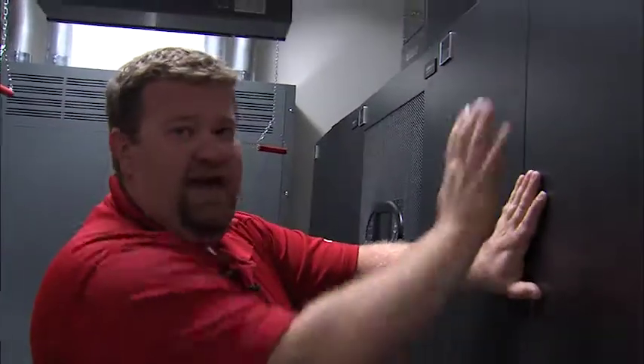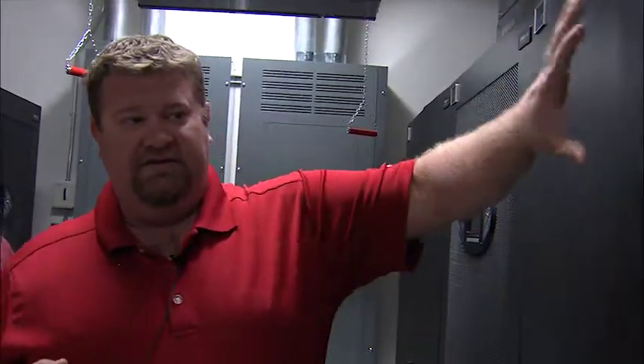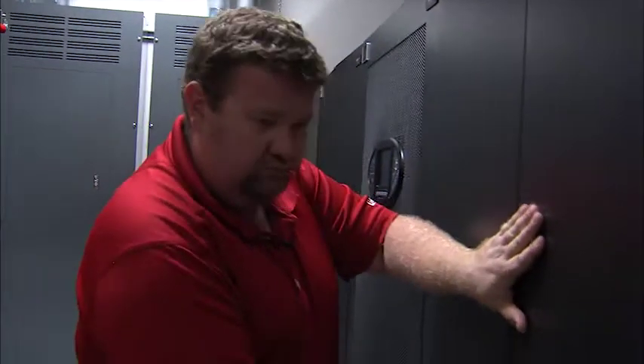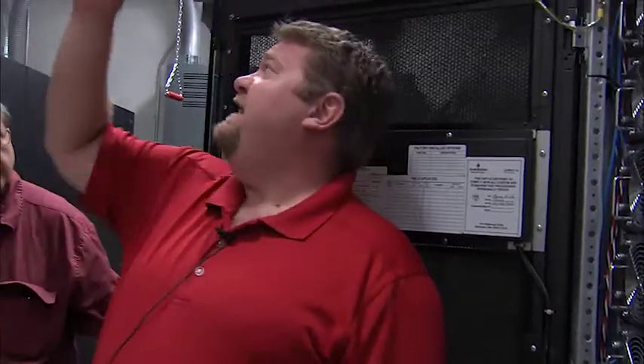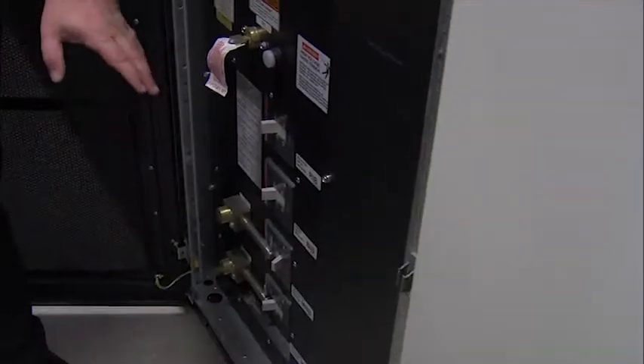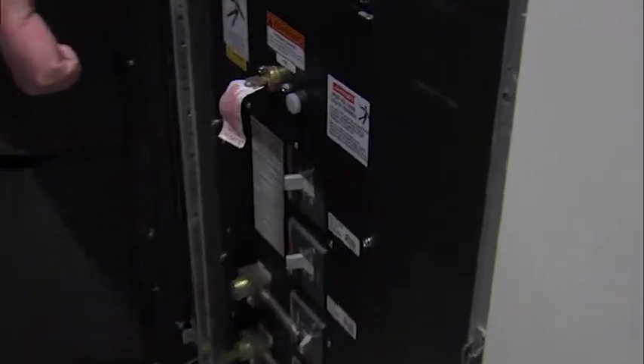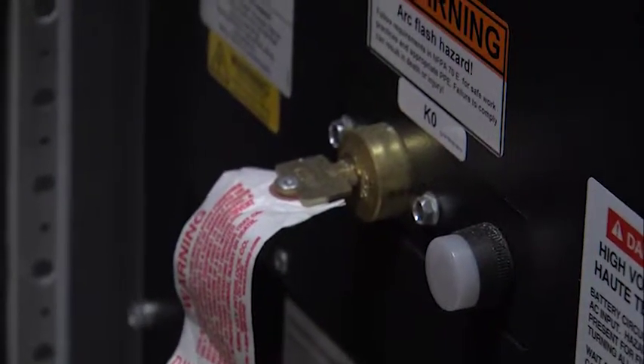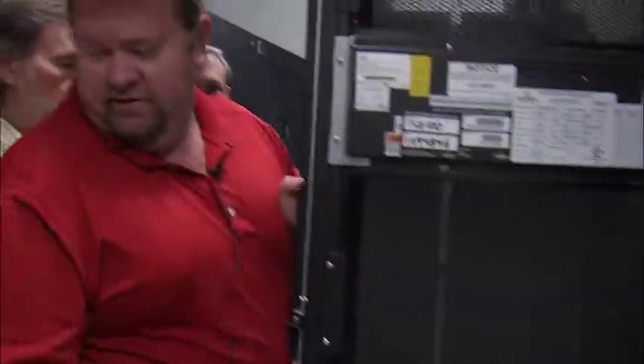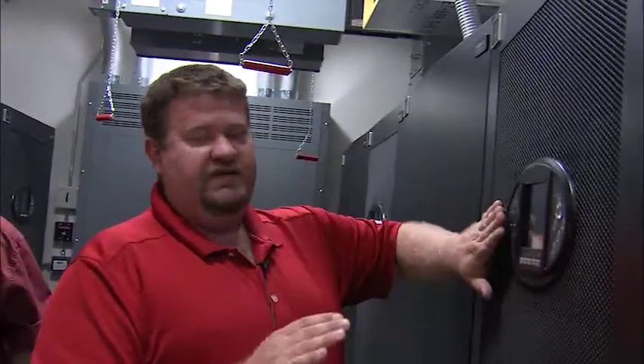Make sense? Okay. This cabinet is tied into that site ID and tag. So when they pull up that site ID and tag, they'll see the UPS and the battery cabinet. We'll go back down here. The system also has an internal bypass, and I'll go over this after. This internal bypass is a Kirk key system, so you can't shut this load off by accident. You physically have to come in here, and put this into bypass.